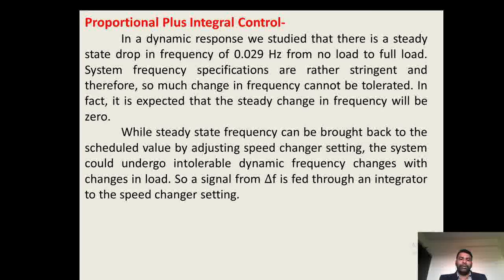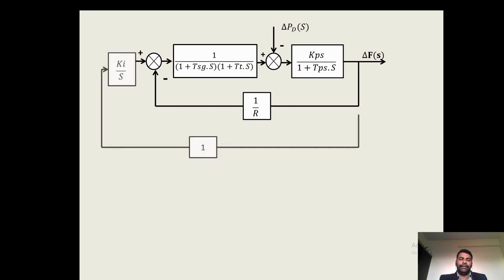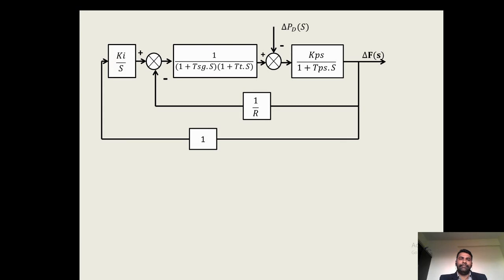The system could undergo intolerable dynamic frequency changes with changes in load. So, a signal from delta f is fed back through an integrator to the speed changer setting. We will now see the changes in the complete block diagram representation of load frequency control. This is the complete block diagram representation. Here, we will add the integrator block before the speed changer setting. This system then becomes the proportional plus integral control action for load frequency control.